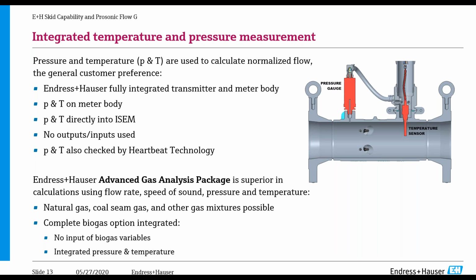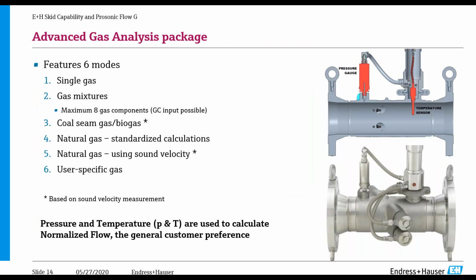We also do a heartbeat check, which I'll mention a little bit later. So we're also checking the diagnostics of the pressure and the temperature. We get some different diagnostic codes and we're able to analyze that inside of our transmitter. If you order the pressure and temperature, we have a special software package. This allows you to do corrected volume flow, so standard cubic feet per minute or hour, and also a gas analysis as far as methane content or combustible content.